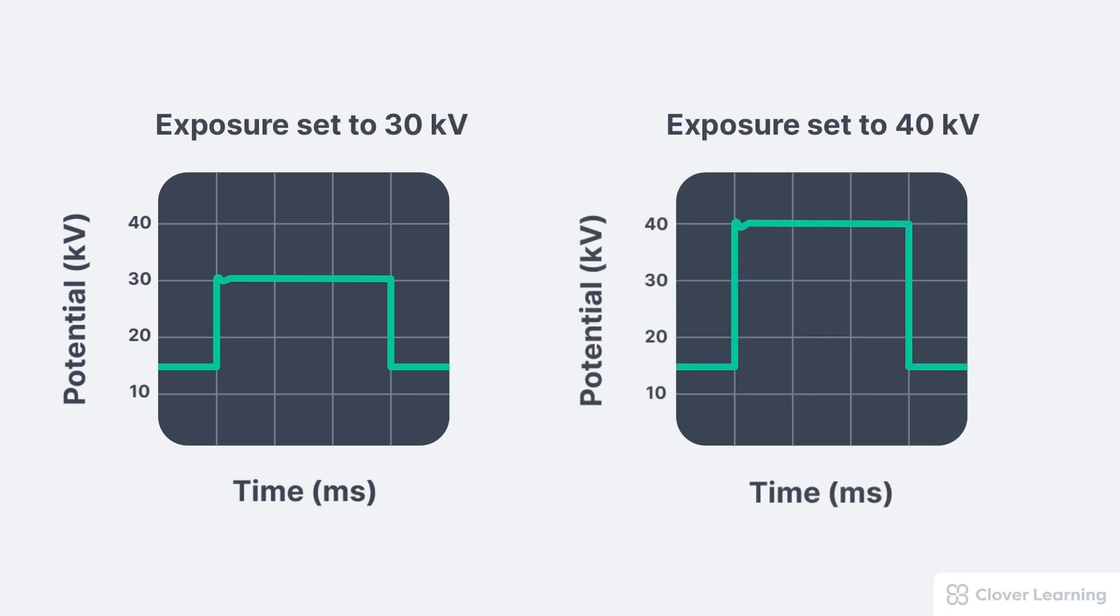Each of these waveforms looks unique. A perfect KV waveform generates the selected KV from the very beginning to the very end of the exposure. This is considered a flat waveform. For example, if the exposure is set to 30 KV, the system should generate exactly 30 KV for the entire exposure.